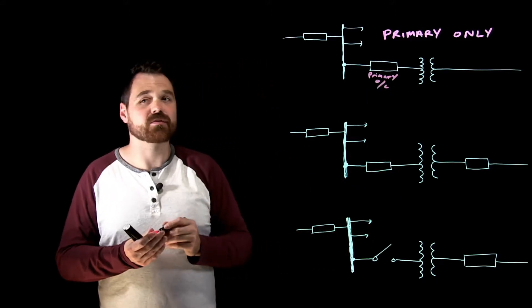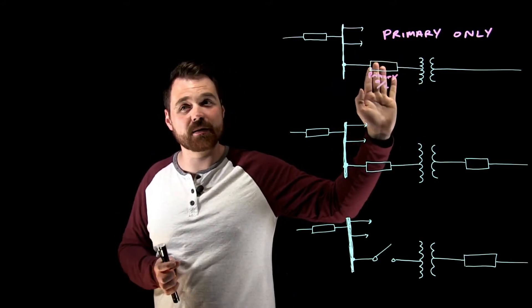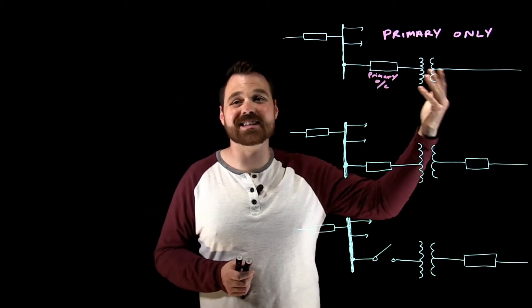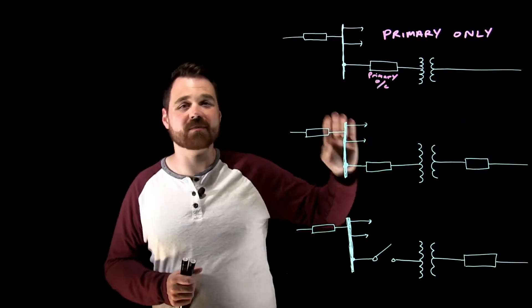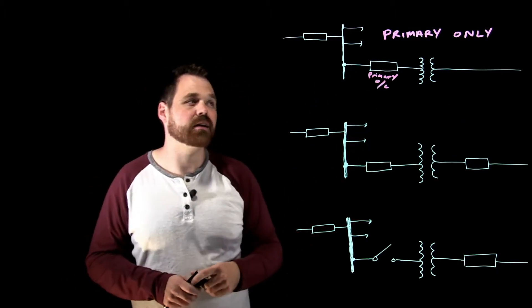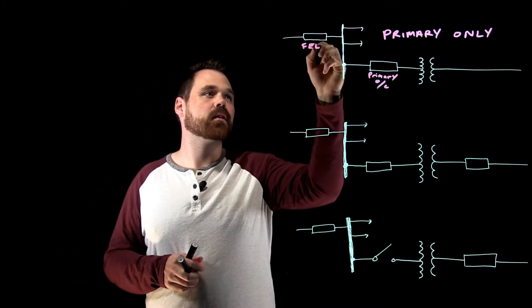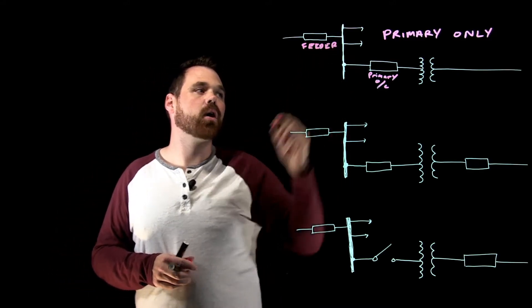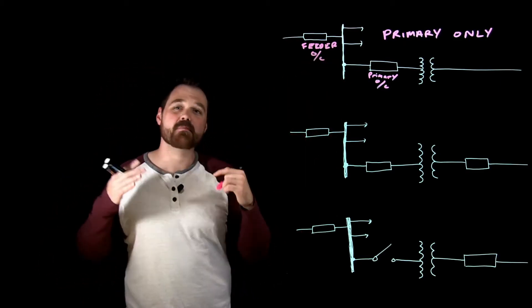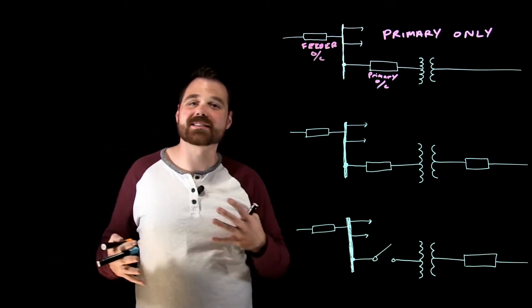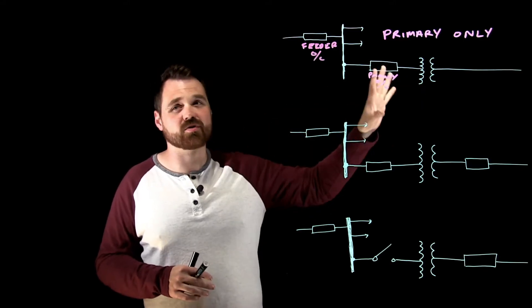The primary OC is going to be directly protecting the transformer. The primary OC not only protects the primary, but it is actually also protecting the secondary, because whatever goes into my transformer has to come out of my transformer. So it's protecting both the primary and the secondary. We would also have this feeder OC somewhere else. This is the most common installation method that you'll see — a primary overcurrent device protecting the primary of the transformer.